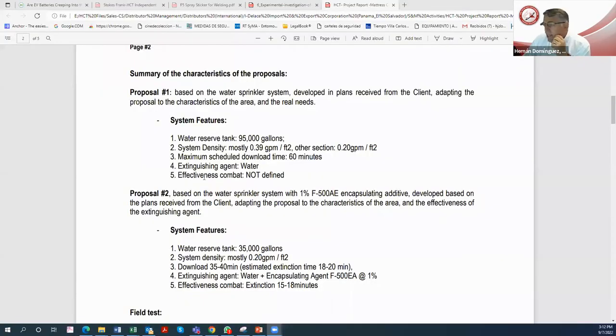Let me show this report, because the insurance company and the fire marshal of Panama wanted to use water, and the first proposal was to use 95,000 gallons of water with a density of 0.39 to 0.4, and the effectiveness of combat was not defined. In testing, we found that with 1,000 liters of water, we could not extinguish the fire. Finally, the proposal with F-500 was 35,000 gallons at half the density, and we were able to extinguish this kind of fire in 15 minutes.